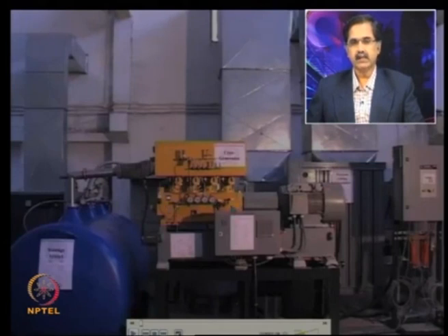Now, this crankcase houses the crankshaft which compresses the helium gas inside this cryogenerator, and this is driven by one motor, and the specification of this motor is around 45 kilowatts. The liquid nitrogen generated from this is around 50 liters per hour, while the gas is charged here at 22 bar. So, that means around 10 to 12 liters per hour from each cylinder.